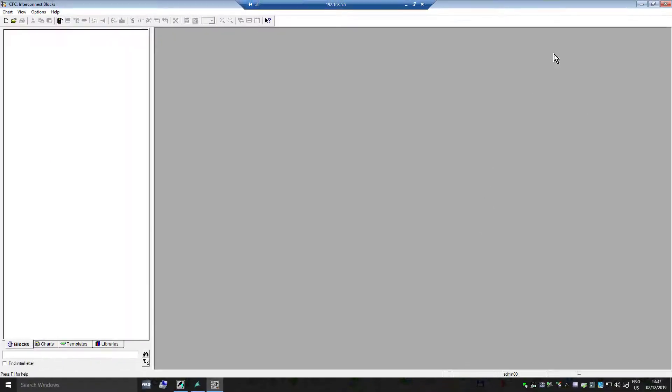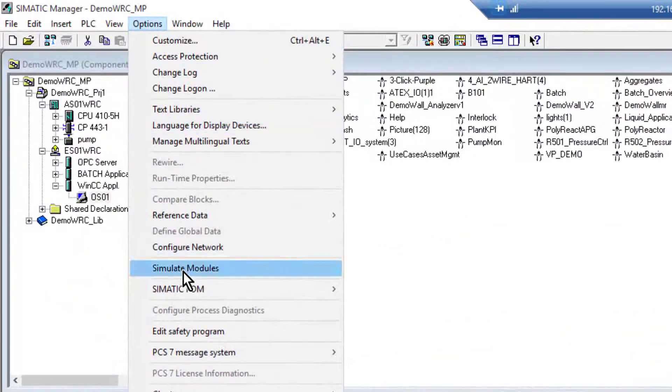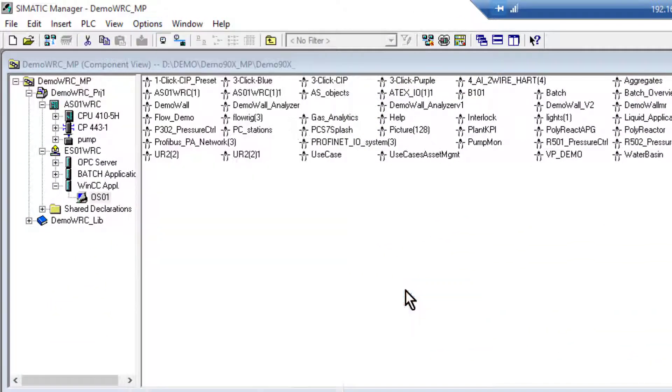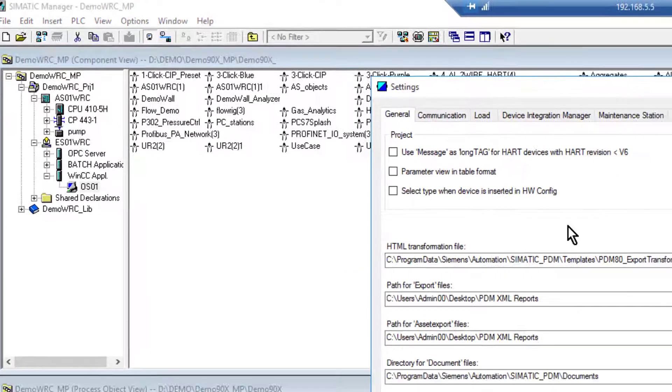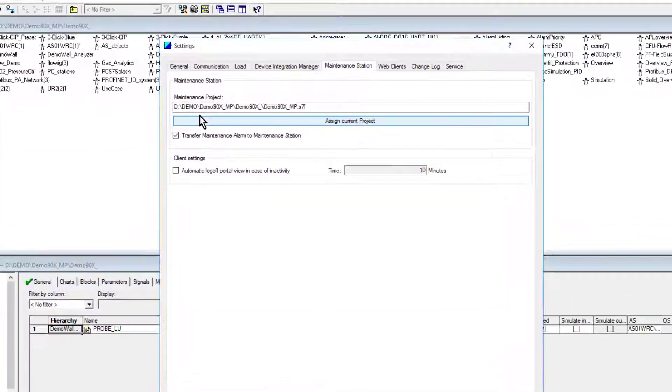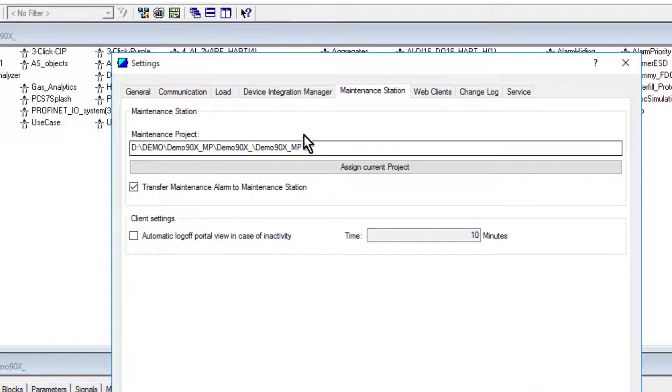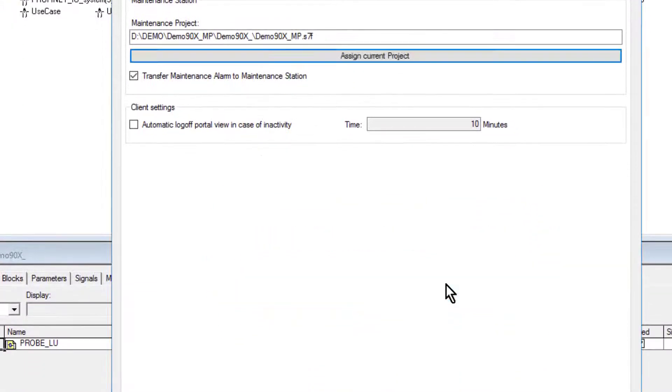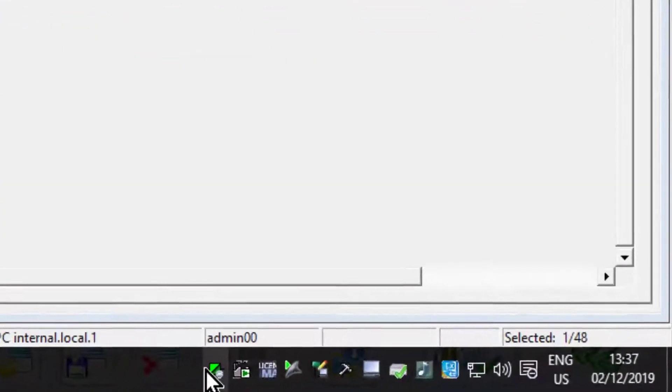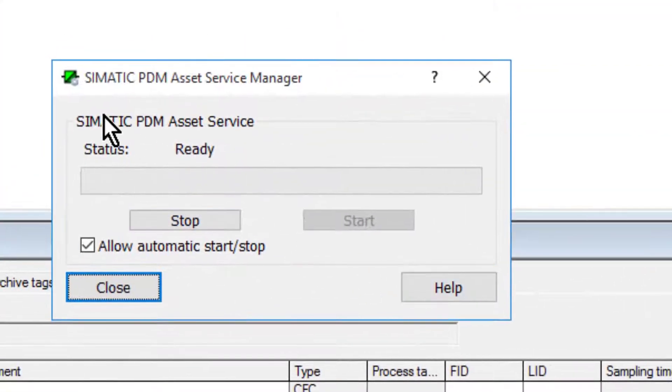So we've created the CFC, we've done the visualization. The last part we need to do is set the maintenance station screens. The first thing we need to do is on the PDM, if we go to Settings. You'll see here Maintenance Station, and let's just make sure we're using the correct project. So we'll assign the current project. Nothing's changed there. If you've made any changes it's always advisable to start and stop the PDM asset service.